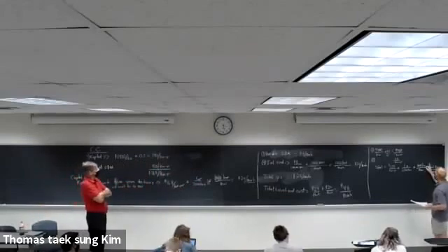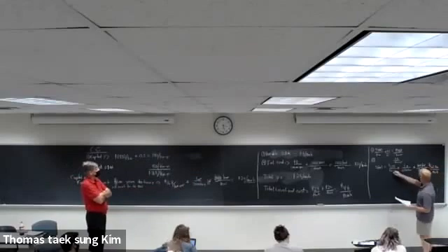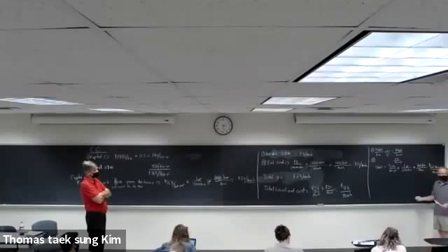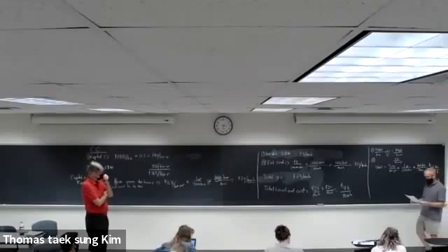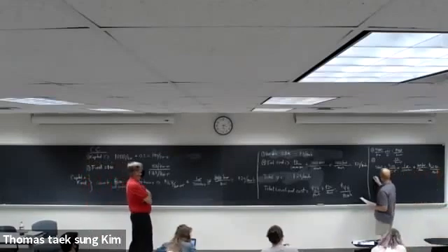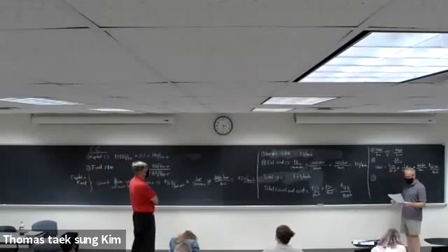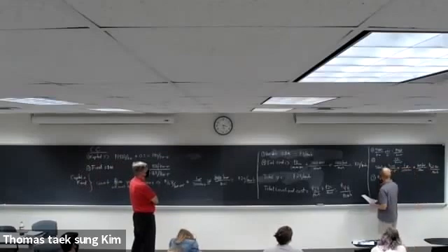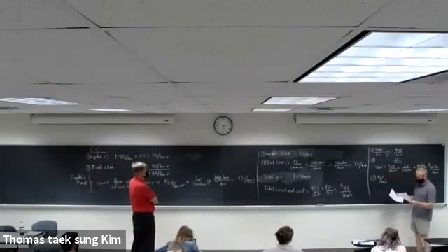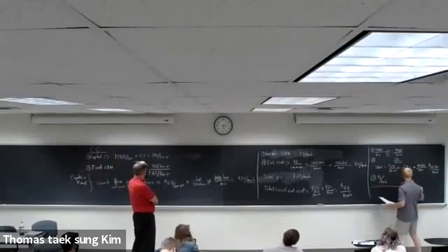So we're going to cancel these things out. Kilowatt canceled out, the year canceled out, hours stayed in there, megawatt hours. 52.50 for that one. And the next one's even easier, because we don't have to worry about the fuel cost, and this variable cost is already $1 per megawatt hour. That's the variable O&M. And so the total cost is the sum of those two things.